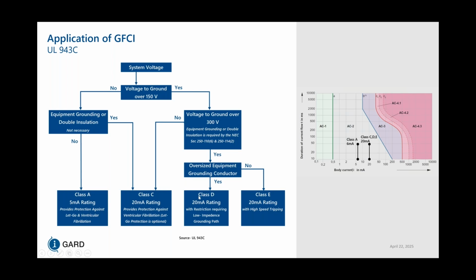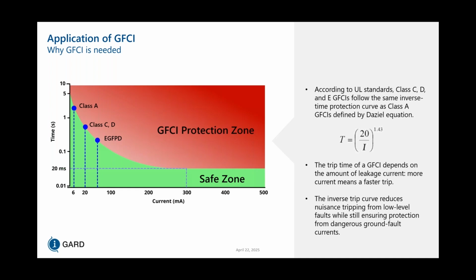All of this information is readily available in UL943C for you to analyze. And on the graph here, we've just illustrated where Class A, C, D, and E fall within the chart that we saw on the previous slide. So according to UL standards, Class C, D, and E GFCIs follow the same inverse time protection curve as Class A GFCIs, defined by the Dalziel equation, and the equation is right there. The trip time of a GFCI depends on the amount of leakage current. More current means a faster trip.